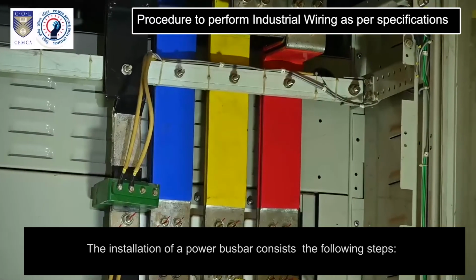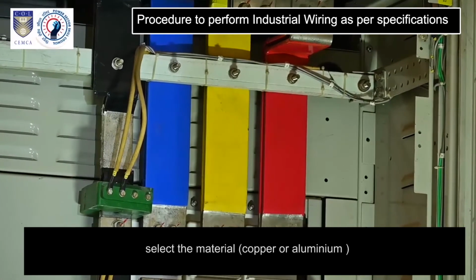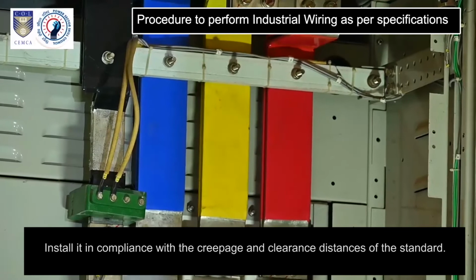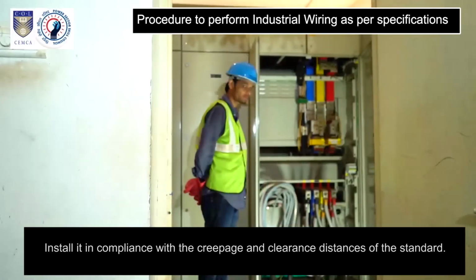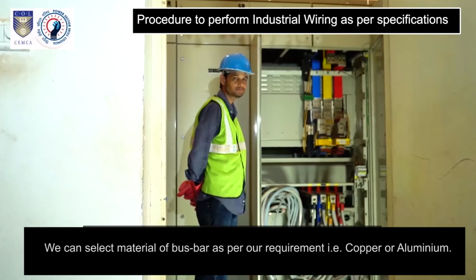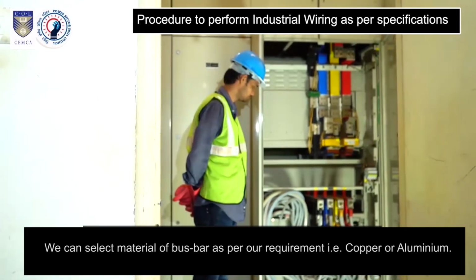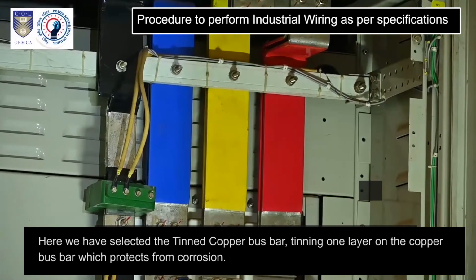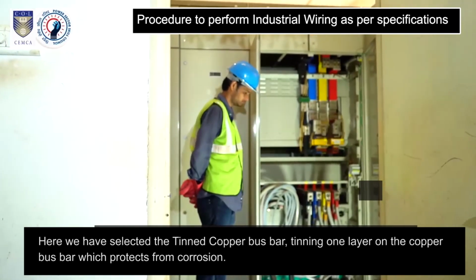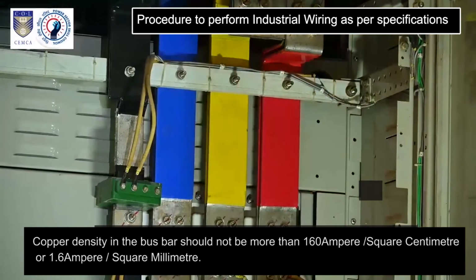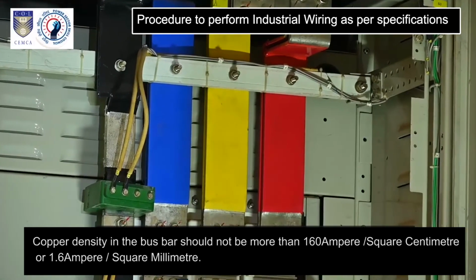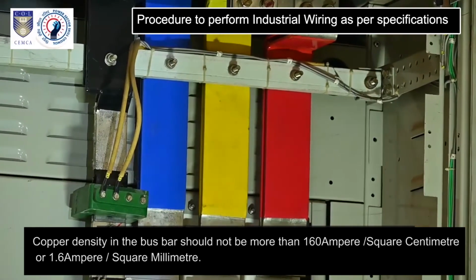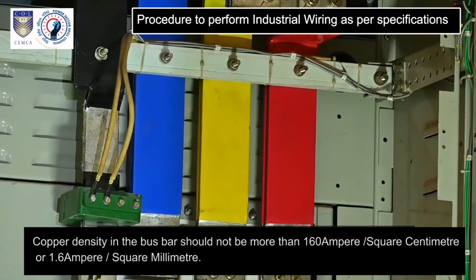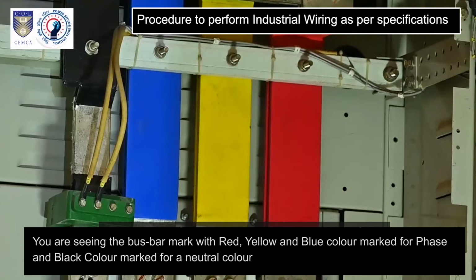The installation of a power busbar consists of the following steps. Select the material, copper or aluminium. Install it in compliance with the creepage and clearance distances of the standard. We can select material of busbar as per our requirement, that is, copper or aluminium. Here we have selected the tinned copper busbar, tinning one layer on the copper busbar which protects from corrosion. Copper density in the busbar should not be more than 160 ampere per square centimeter or 1.6 ampere per square millimeter. You're seeing the busbar marked with red, yellow and blue color for phase and black color for neutral.